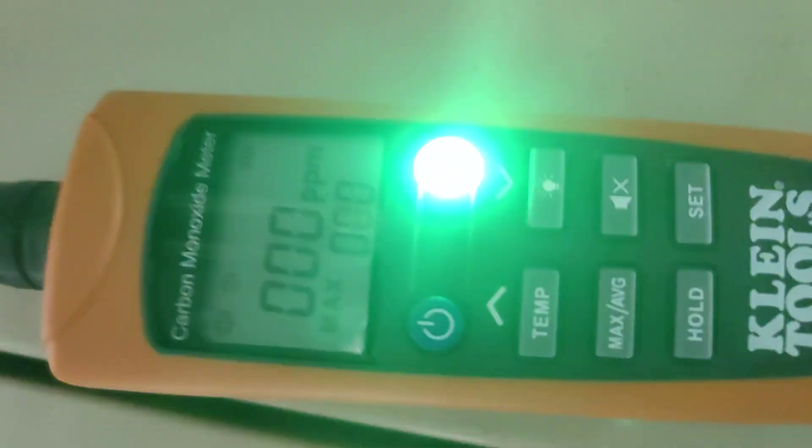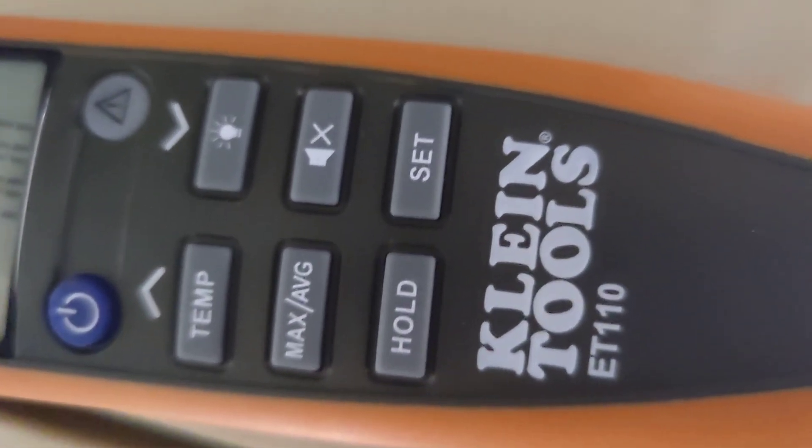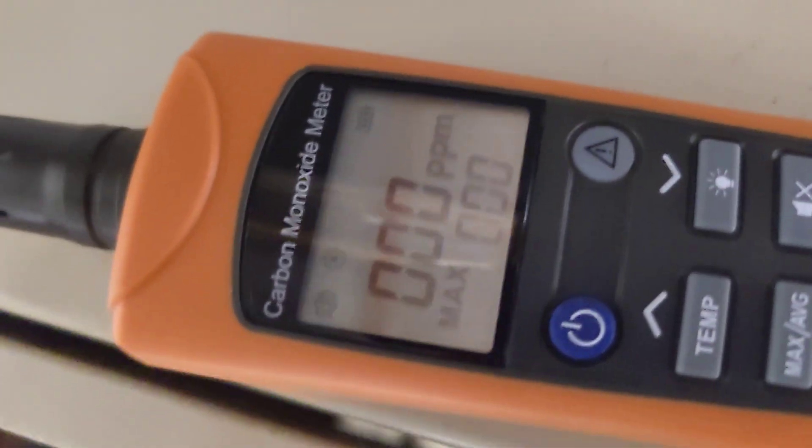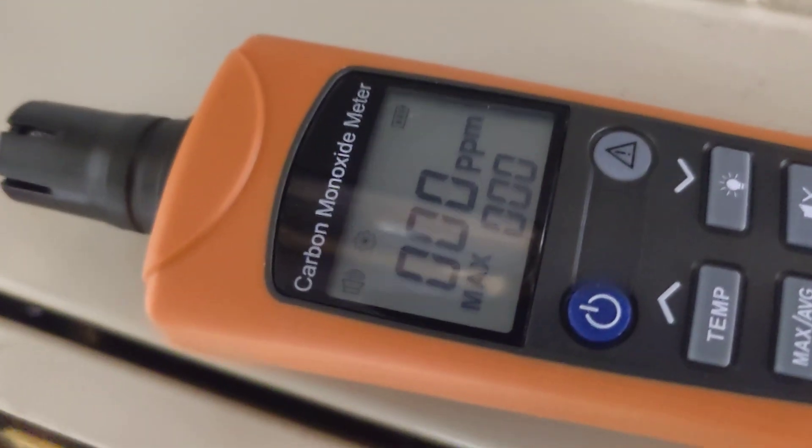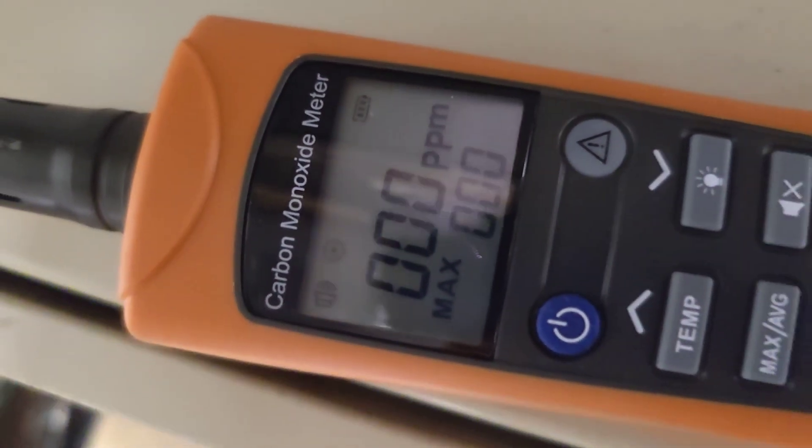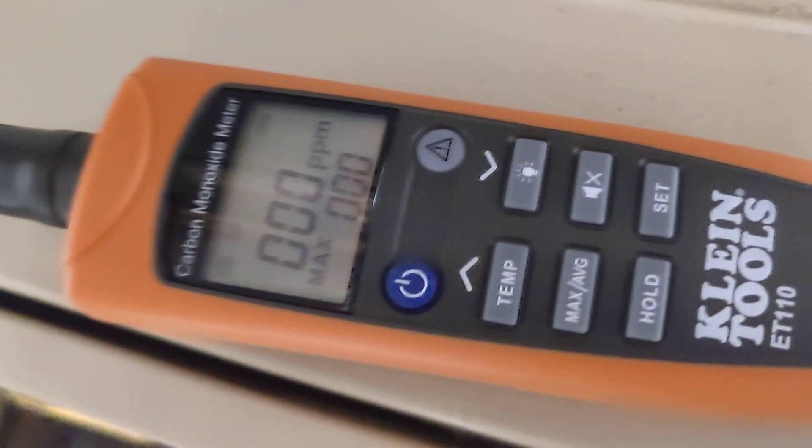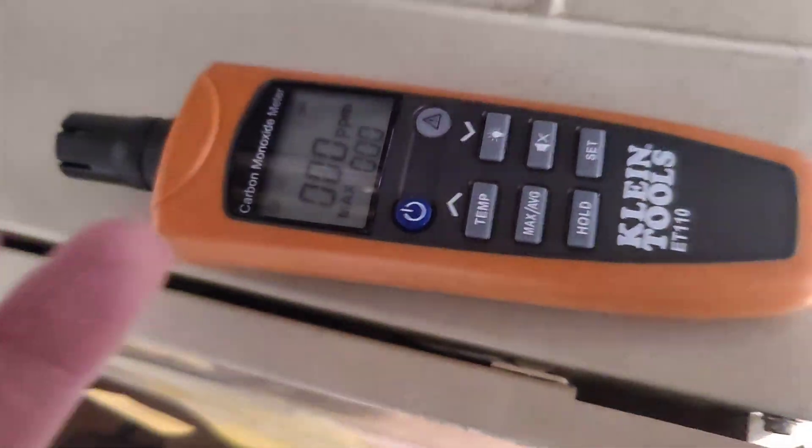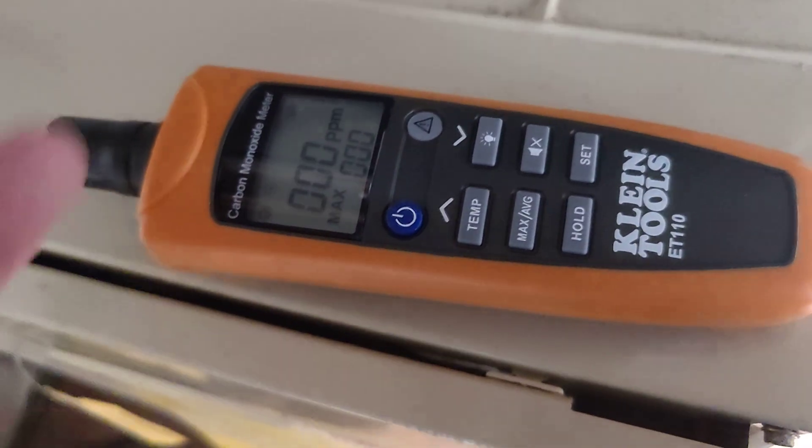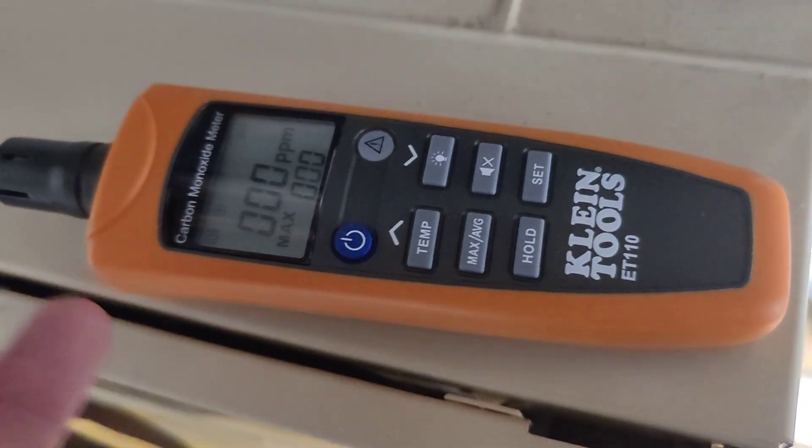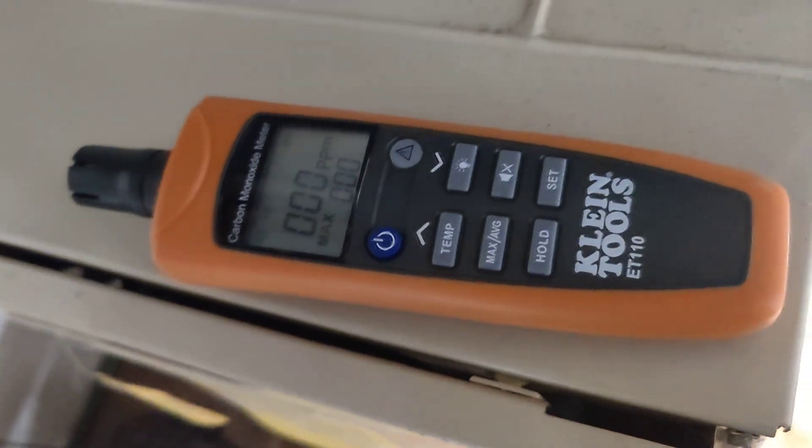This ET110, very simple tool. You can clearly see I'm not getting anything, not even one parts per million, so that means I'm not getting any rollout at all. I can actually find out if I'm having rollout issues without even taking the cover off the furnace.